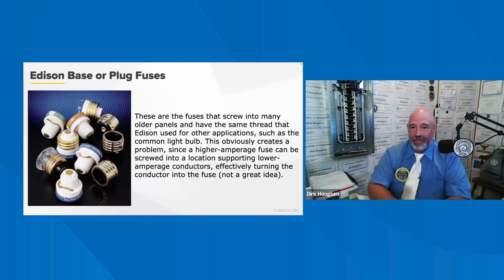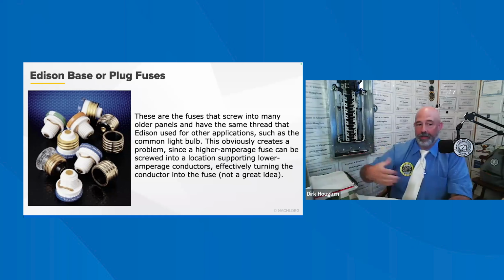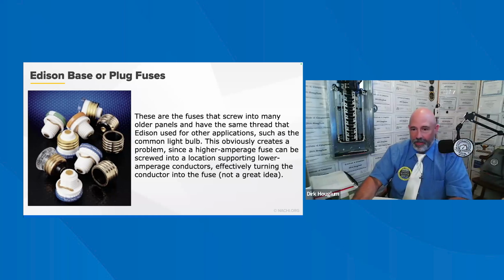Like I said, in the 1950s and 1960s you'll see these Edison fuses, and they are still common, but not as common as they used to be. These were the S-type fuses, which also had the benefit of stopping someone from repairing a blown fuse. They also made ones that were kind of like your circuit breaker, so you could just push it in once it tripped, but they never really caught on. And now when I see it, I just say it needs to be upgraded.